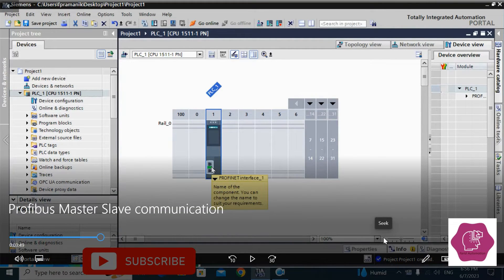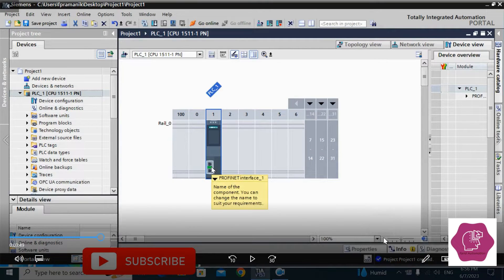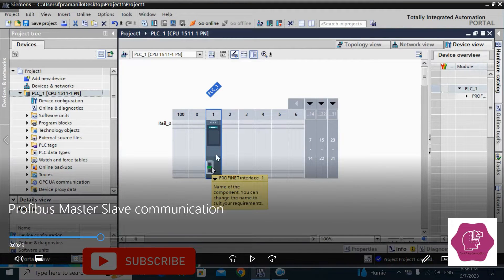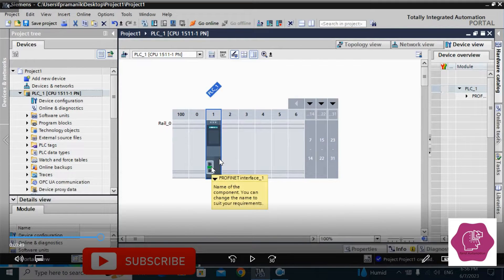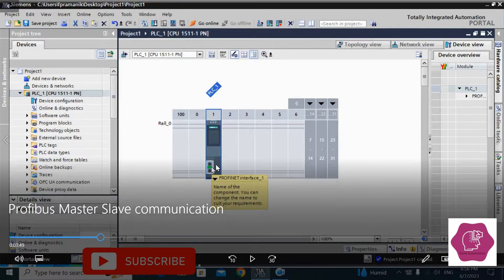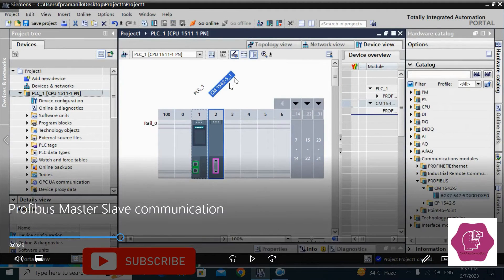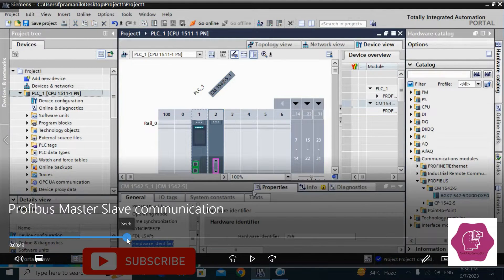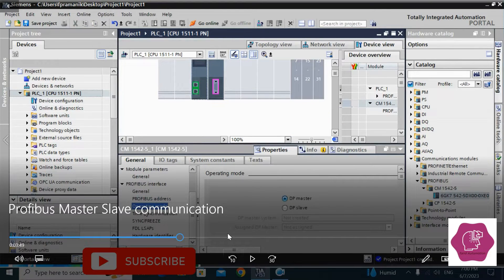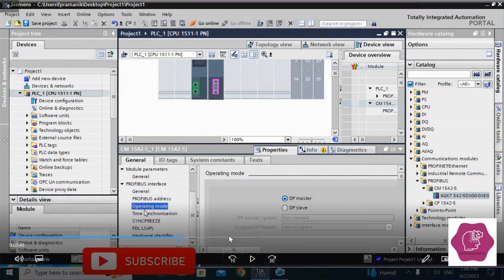Welcome back. In this demo video we will discuss Profibus master-slave communication between Siemens PLC and ABB PLC — this is part two. In part one we already discussed mostly the configuration on the Siemens PLC side. The Siemens PLC is CPU 1511 PN, which has no Profibus port, so we have taken a communication module CM1542-5 and configured it as a Profibus DP slave. Today we will discuss how to configure that Profibus master module in ABB PLC to communicate with Siemens PLC.